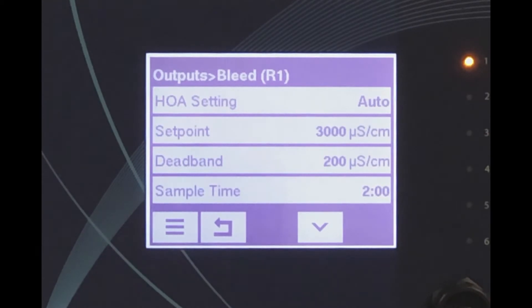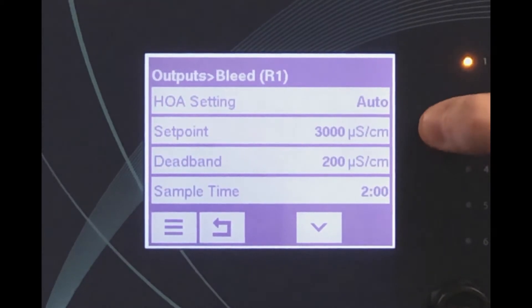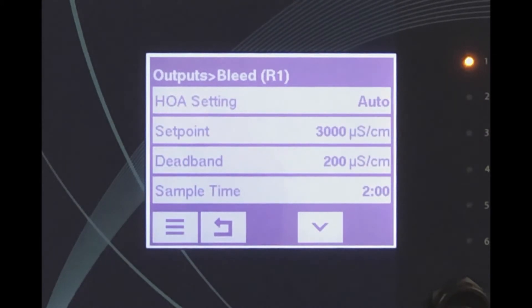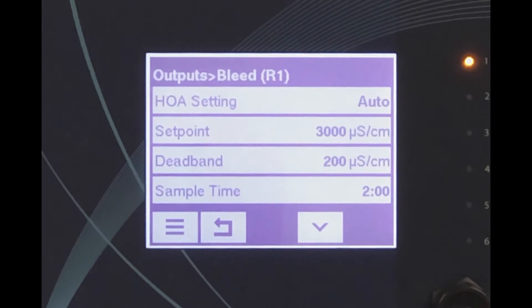The controller will measure the boiler conductivity and compare it to set point. If the sample is under the set point, the blowdown valve will close at the end of the sample time. If the sample conductivity is over the set point, the relay will stay on and the valve will stay open until the conductivity has decreased below the set point by the amount of the dead band.